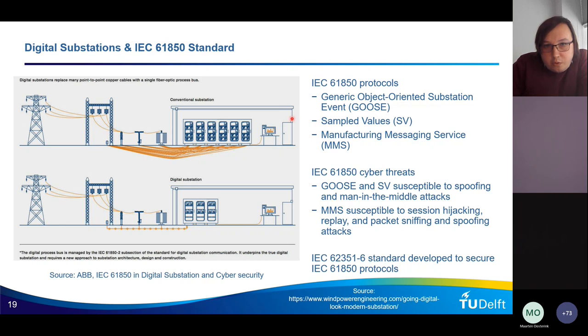Now, as we embrace digitalization, we replace all this hard wiring with digital communication. So this would be a fiber optic. It's much cleaner and it provides more data faster. And we use various communication protocols like IEC 104. And in our case, we use IEC 61850.